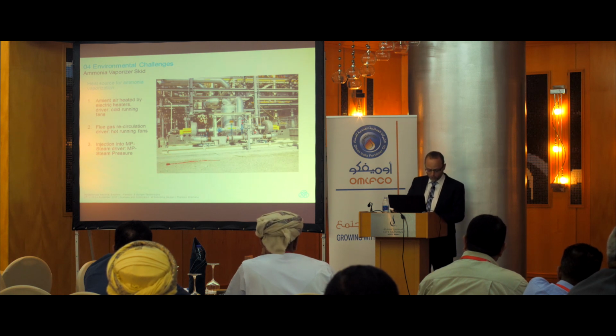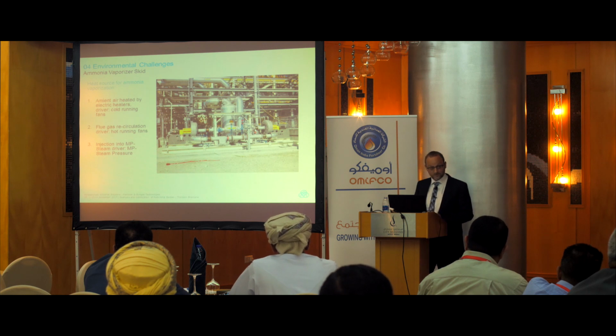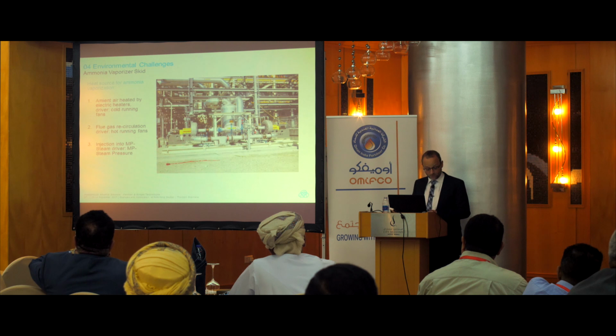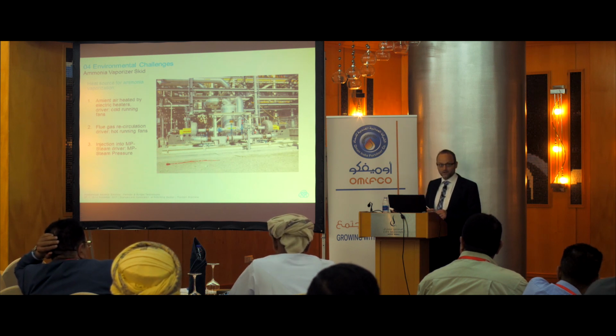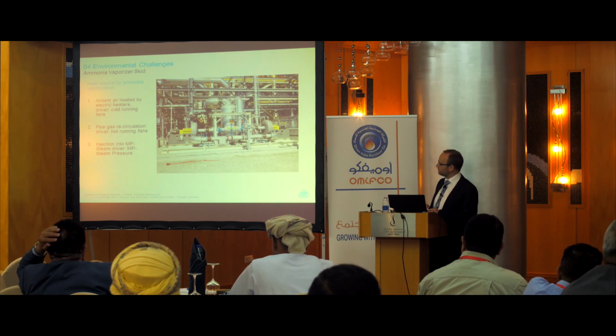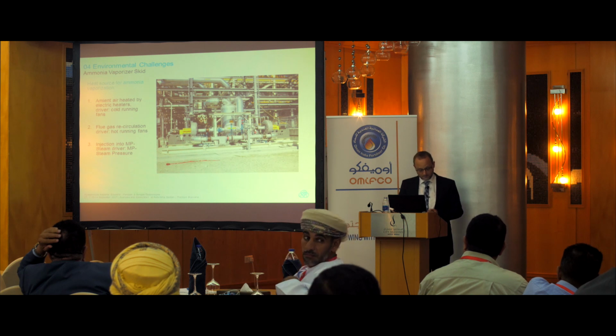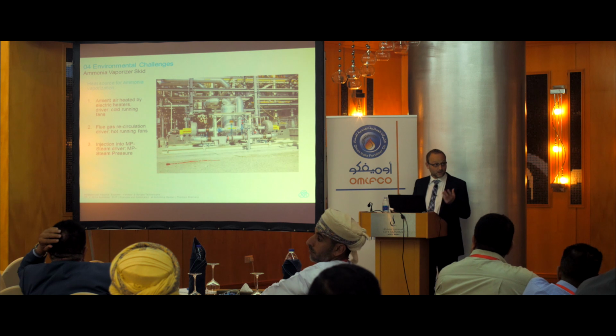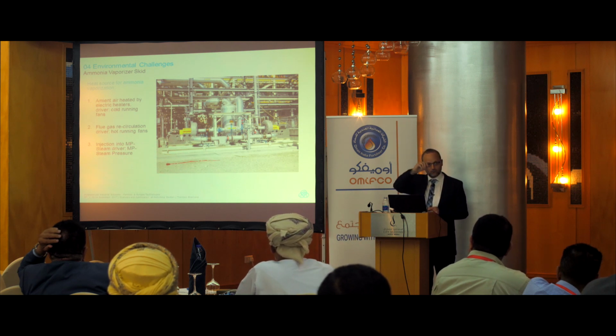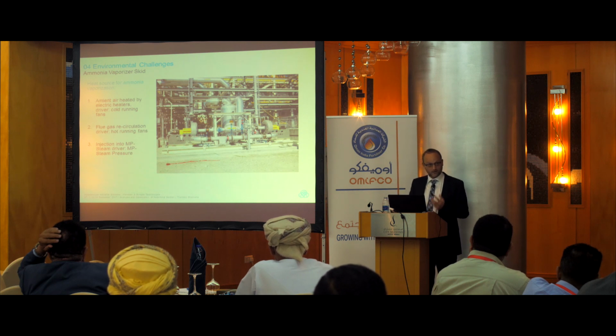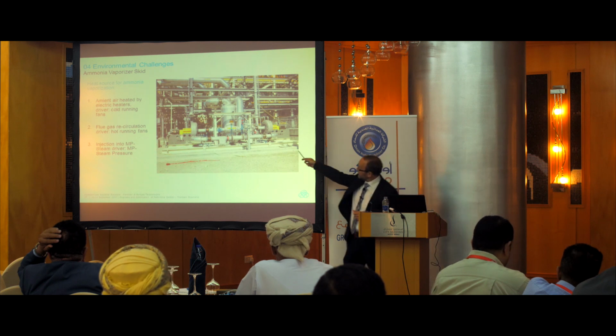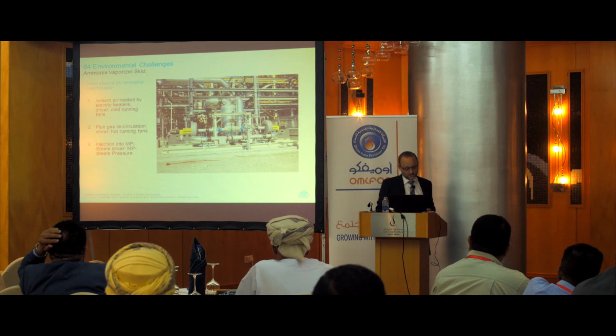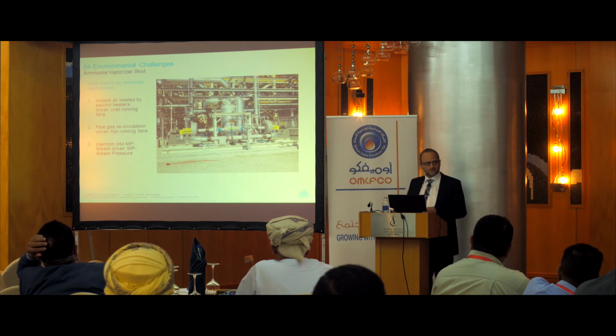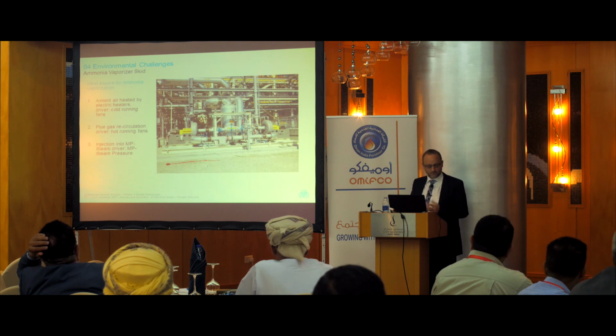For the necessary vaporization of the ammonia water, different options are available as a heat source for the evaporation. First, electric heaters, which are commonly used to preheat ambient air. We have used this only once for a very small unit. A better heat source is, of course, the flue gas inside the convection bank. It is there already for free. We now just need to recirculate it from the convection bank through the skid and back to the convection bank injection grid. And this example is with flue gas recirculation here. And as the last option, we have superheated MP steam. This eliminates the need for fans and makes this skid very easy for operation and also for maintenance. Of course, MP steam must then be available from the plant itself.